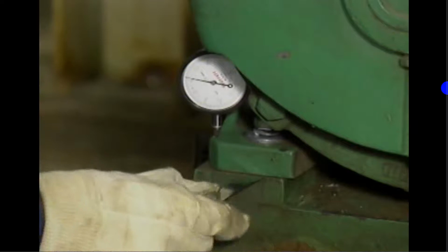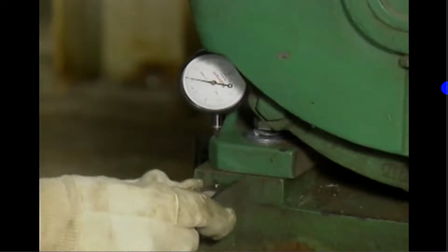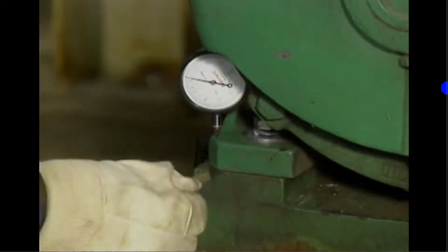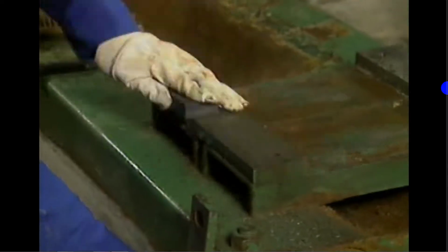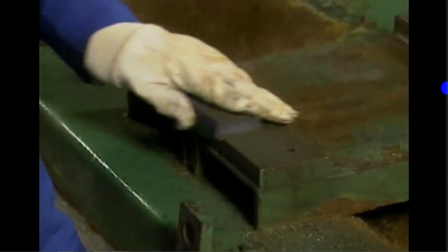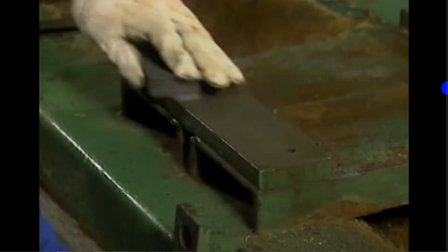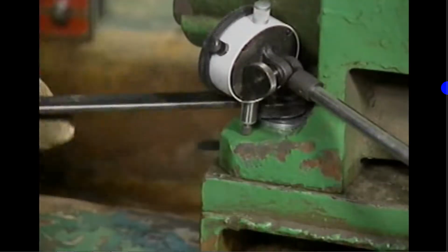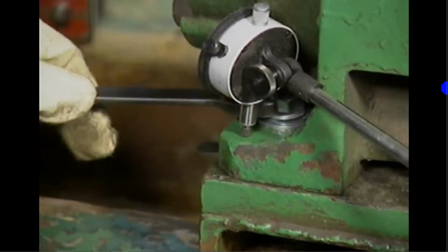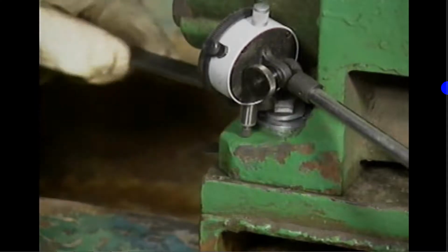Now, if a soft foot is detected and the feeler gauge won't slide evenly under the foot, then the foot may not be parallel to the base. In that case, the foot or the seating surface of the foundation may have to be reworked, or the foot may require special shimming. In any case, once corrections have been made, the procedure should always be repeated to verify that the soft foot condition has been eliminated.